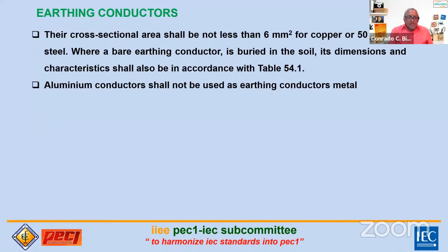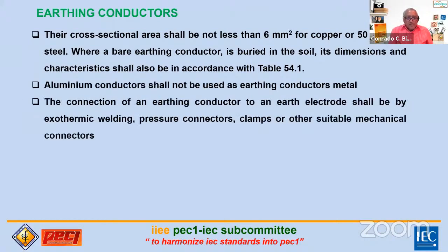For what reason? Alam natin aluminum, pag nasa lupa yan, naibaon siya or whatever, kakainin siya ng corrosion. So magkakaroon tayo ng problema. Mas mabilis na makorrode ang aluminum. So the connection of the earthing conductor to the earth electrode shall be by exothermic welding, pressure connectors, clamps, or other suitable mechanical connectors. So very important.